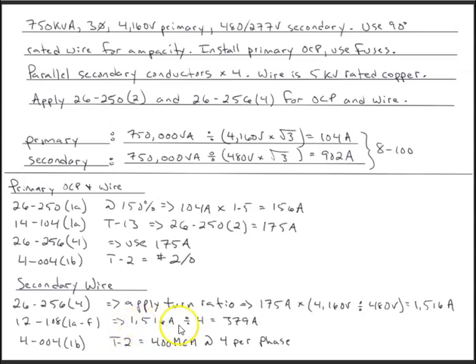So we're taking 1,516 amps, we're dividing it by 4 because we are paralleling by 4. So we end up with 379 amps, and that's going to be the value for one of the 4 conductors. So we go over to table 2 and we size our conductor according to the 379 amps. So 379 amps gives us a 400 MCM, and it's going to be 4 per phase. So what that means is we're going to have 4 400 MCMs for the A phase, 4 400 MCMs for the B phase, and 4 400 MCMs for the C phase and the parallels.